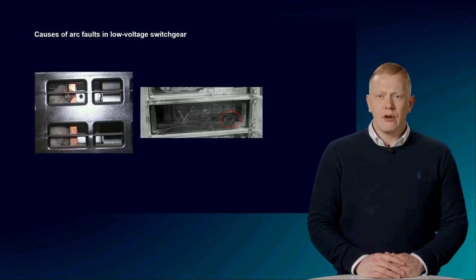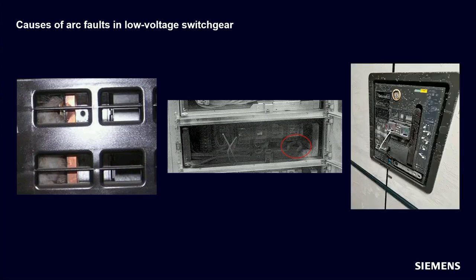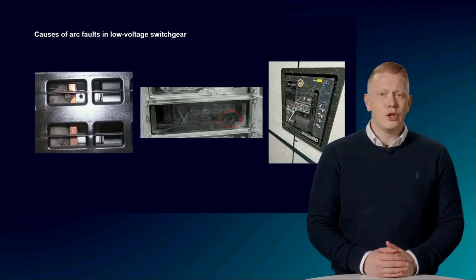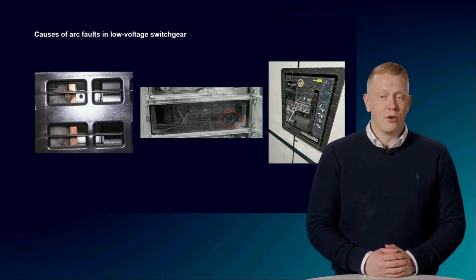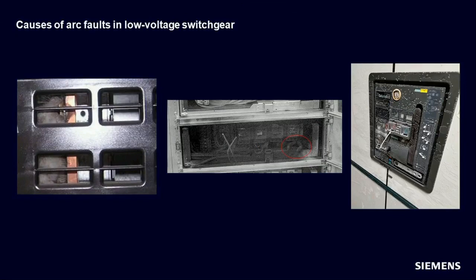Handling errors are also a possible source of risk — for example, incorrectly carried out maintenance work or non-compliance with the environmental conditions for which the system is designed, like a system that stood in a building without windows and heating and became iced over. Errors in planning also pose a further risk, for example due to incorrect dimensioning of equipment or cables, which in an extreme case can lead to overload, failure, and short circuit.